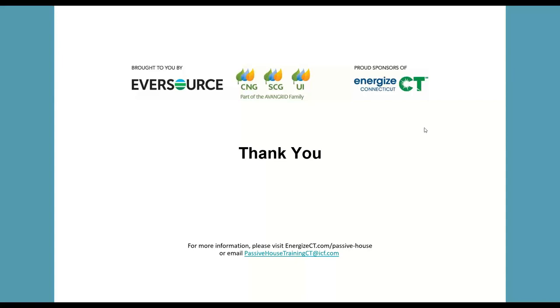I'll mention, in a similar way, heat pumps provide heating and cooling as well. The ERVs and HRVs provide a method of transferring heat energy from incoming air to outgoing air, whether that's cool or cold air. They're always transferring heat, but whether that goes to the incoming or outgoing air depends on the season. They don't have any heating elements that provide additional heat beyond what's already in the air. Your heat pump unit is what provides the additional heating or cooling.